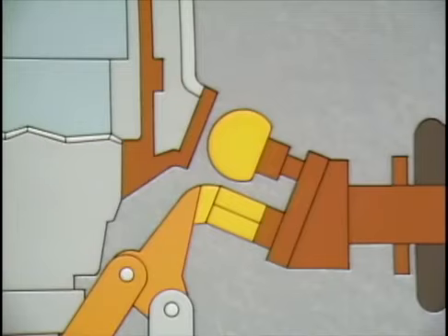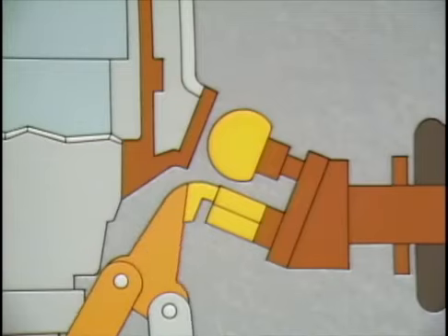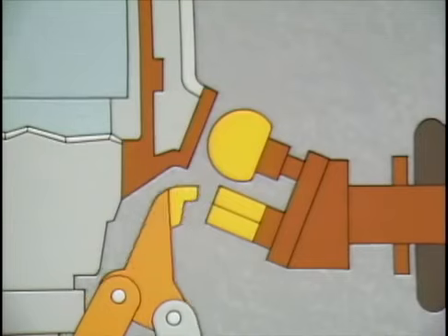is created. When the breaker trips, the contacts begin to move apart. The main contacts separate first. Arcing does not occur because the circuit is still complete through the arcing contacts. As the contacts continue to move, the arcing contacts separate, creating an arc. The arc is quickly extinguished by a number of features that work together.